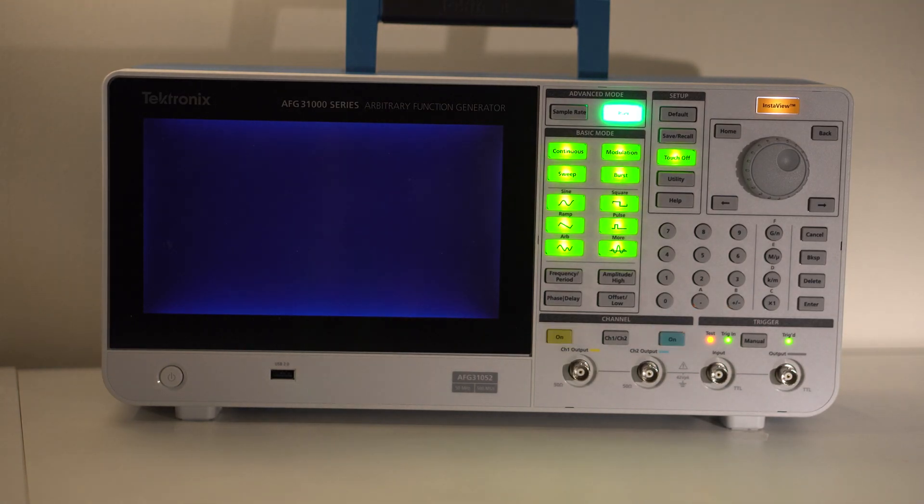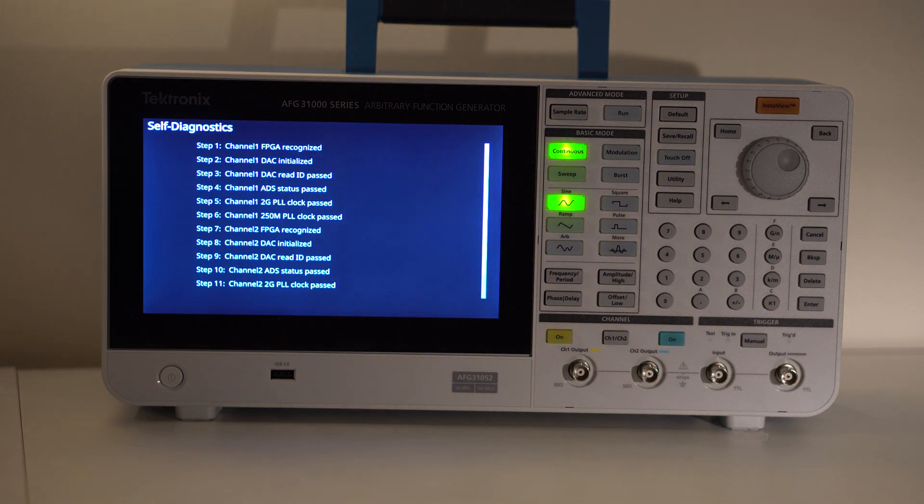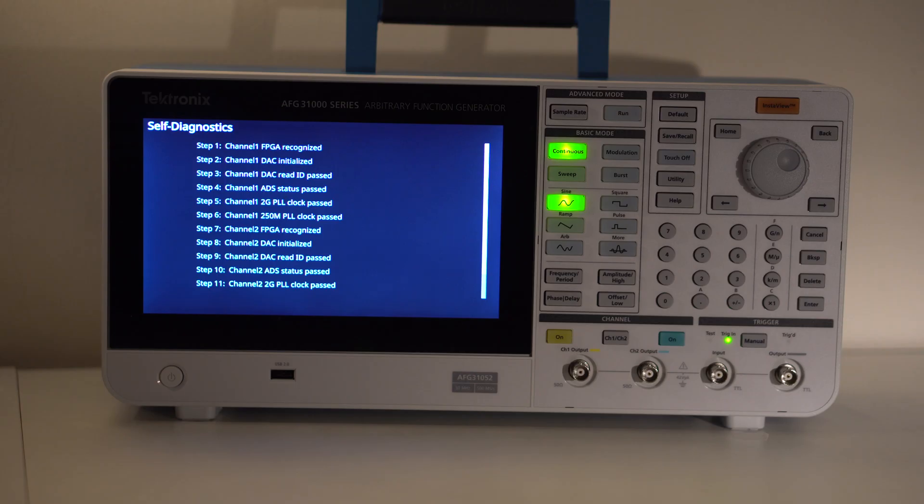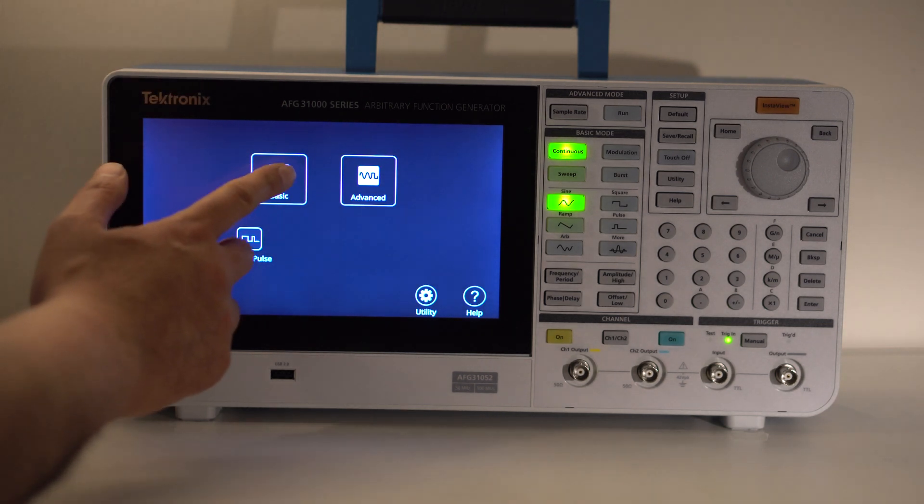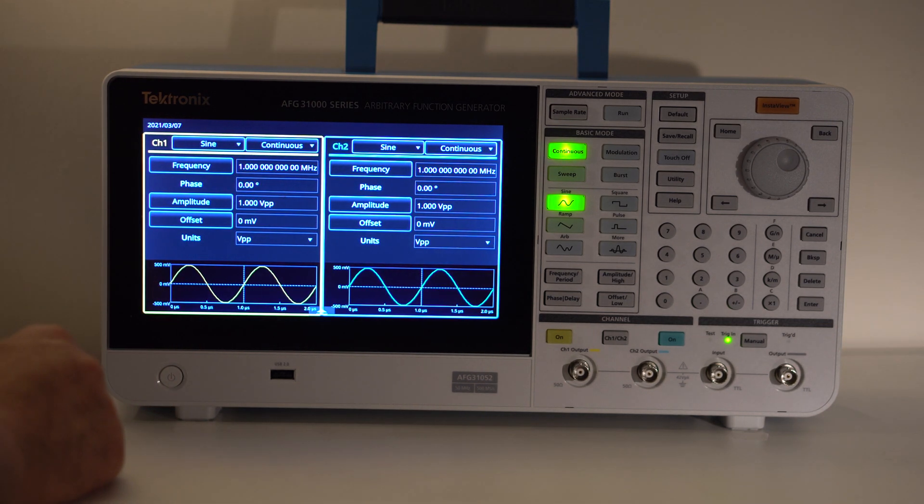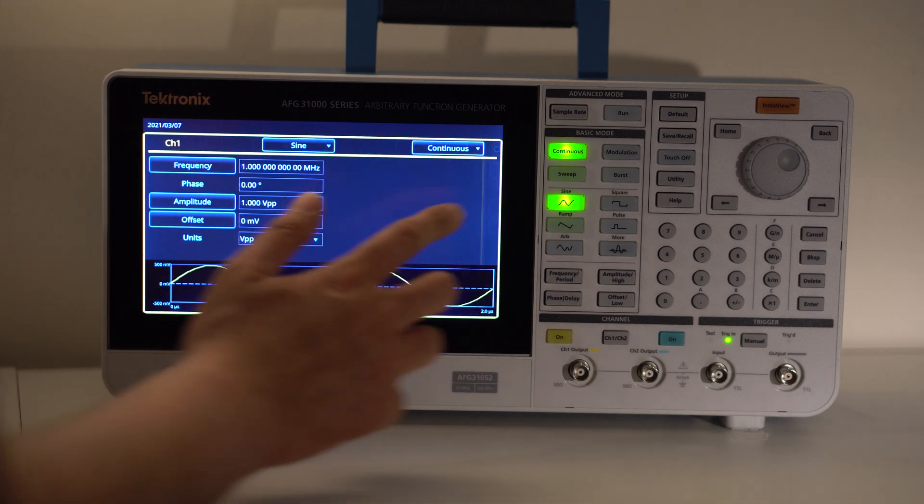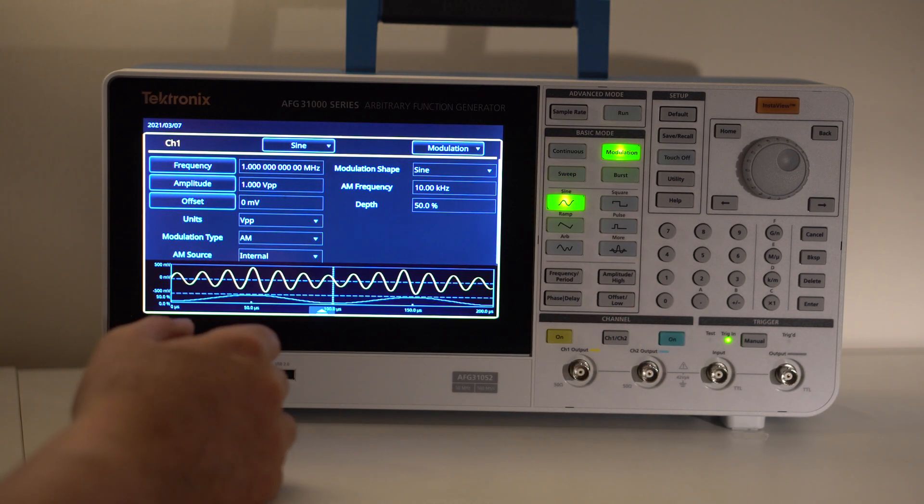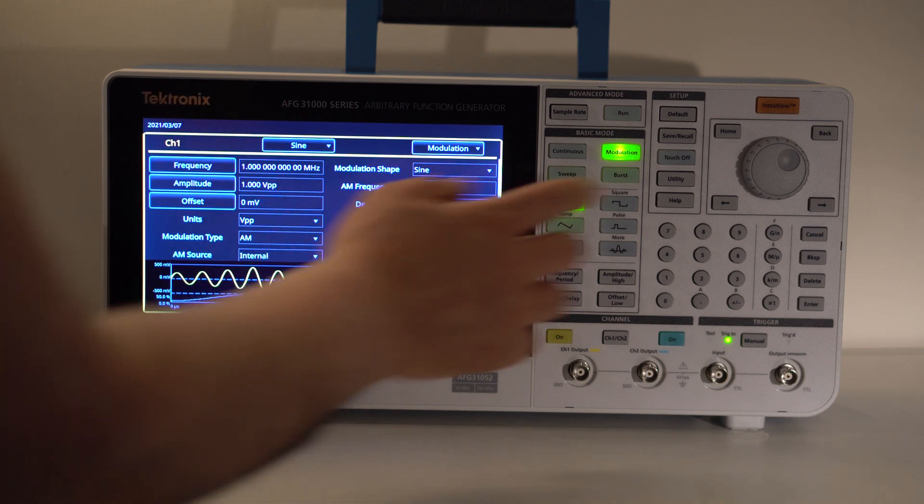The AFG31K is a very modern, recent instrument series, costing from about $2k for the upgradable bandwidth single-channel model up to $15k USD for the full-featured dual-channel version. The key benefits are a sample-based mode called Advanced Mode that allows for amplitude and sample-perfect sequencing from files, a monitoring capability called InstaView, extremely low jitter down to 2 picoseconds, and custom apps capability allowing users to build unique testbeds with extra functionality.